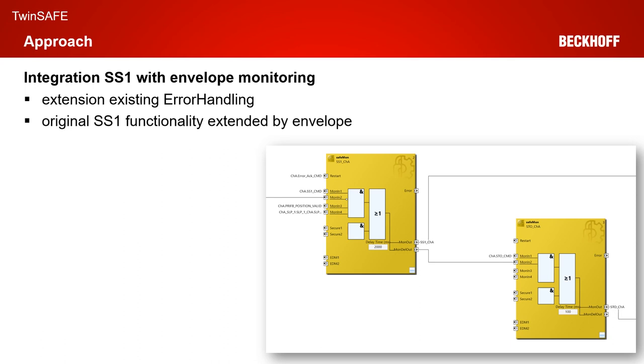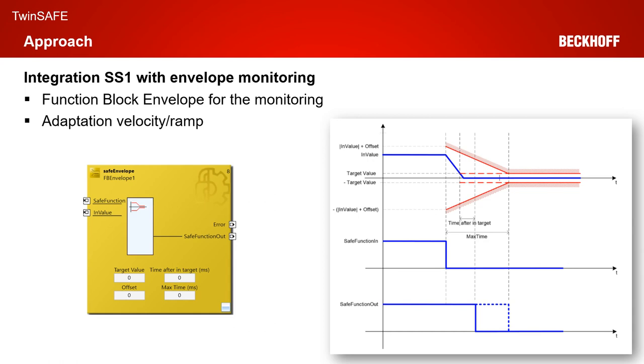Within the error handling, as you see in the right corner, we have two monitor function blocks realizing the standard SS1 functionality. This is exactly the point where we want to integrate our SS1 with envelope monitoring. Basically, we break up the original SS1 connection between the two SafeMonitor function blocks and we integrate our envelope monitoring.